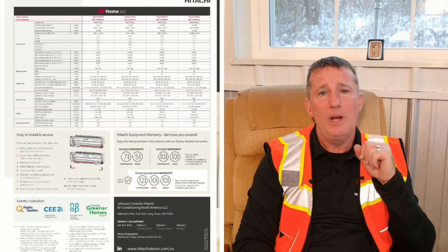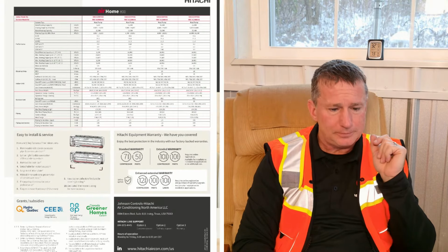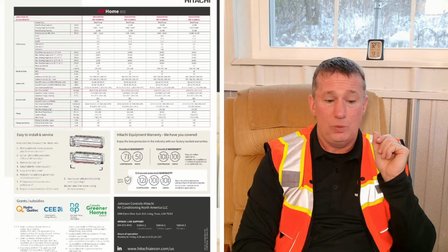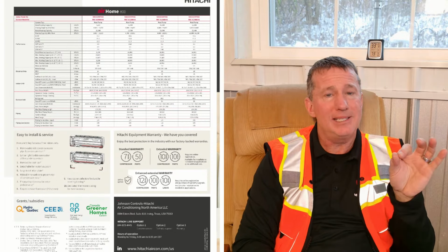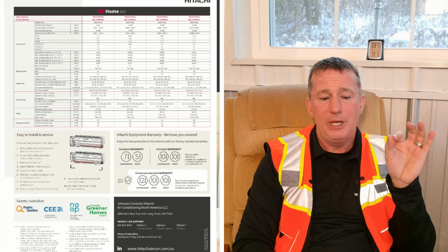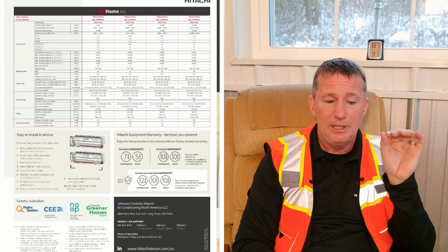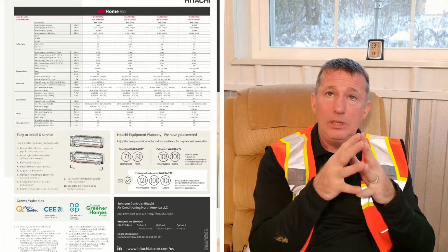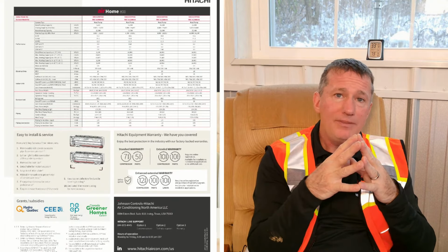So we're looking at this second column here. This is the 12,000 BTU unit. This 12,000 BTU unit is rated at 12,500. It has a cooling capacity - this is the important part - between 5,000 BTUs and 14,000 BTUs. So when we're looking at our inverters, we have to understand what their capacity range is.